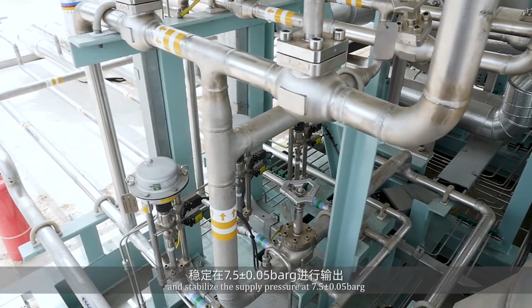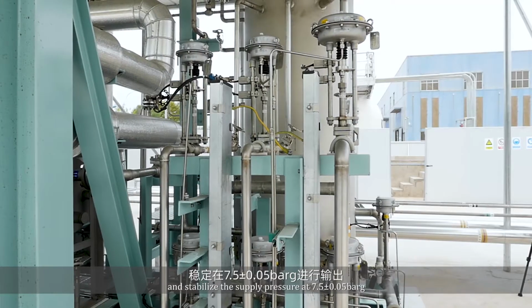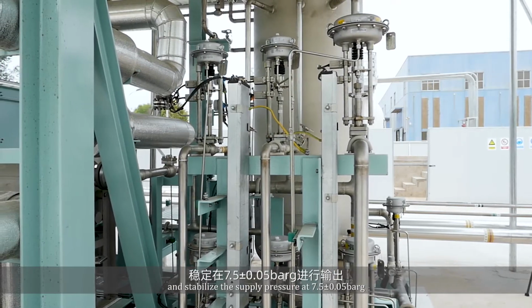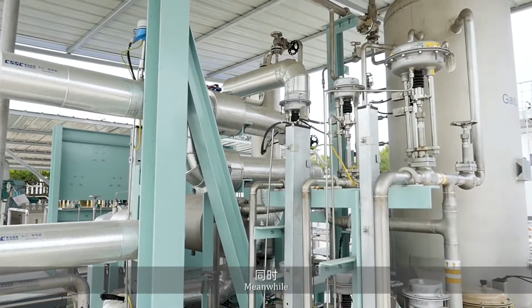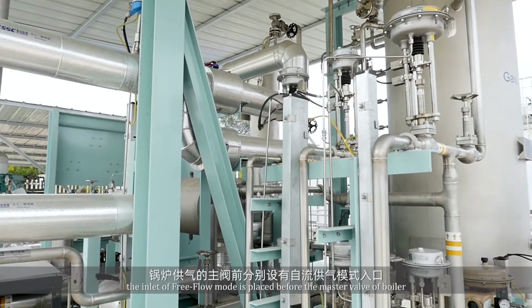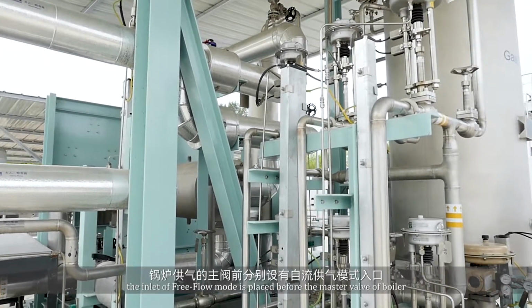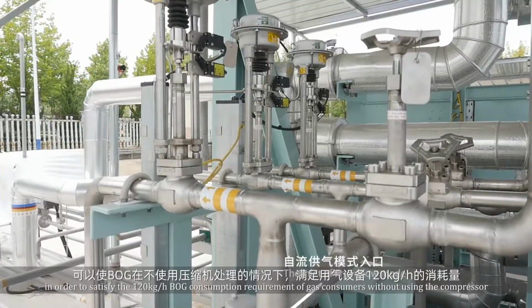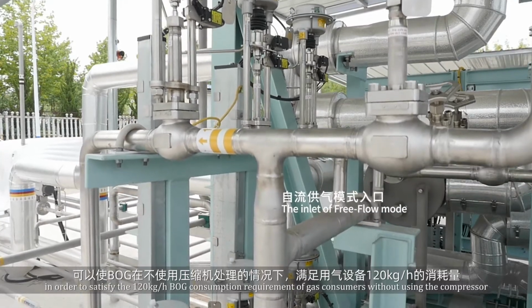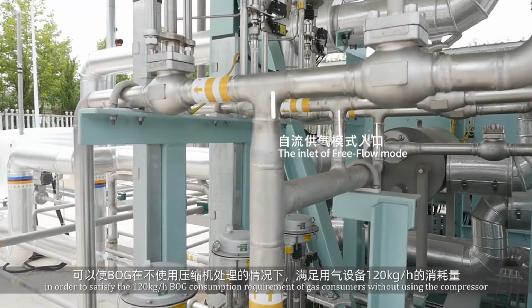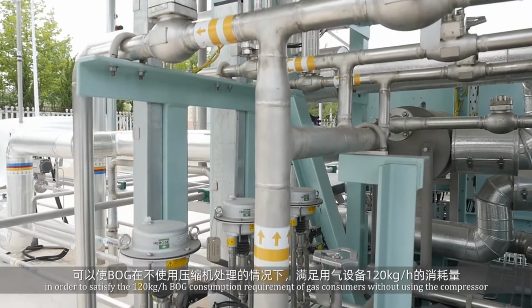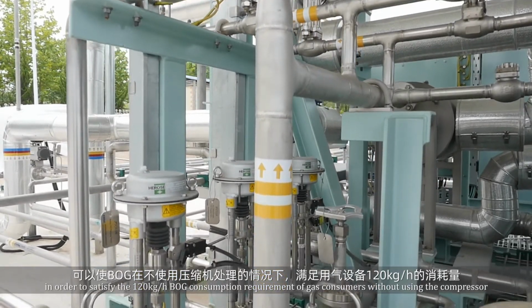and stabilized supply pressure at 7.5 plus or minus 0.05 bar. Meanwhile, the inlet of free flow mode is placed before the master valve of the boiler in order to satisfy the 120 kg per hour BOG consumption requirement of gas consumers without using the compressor.